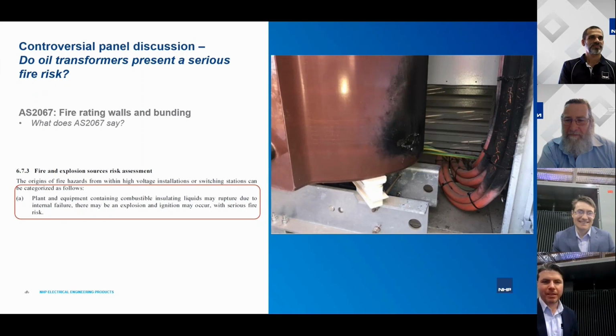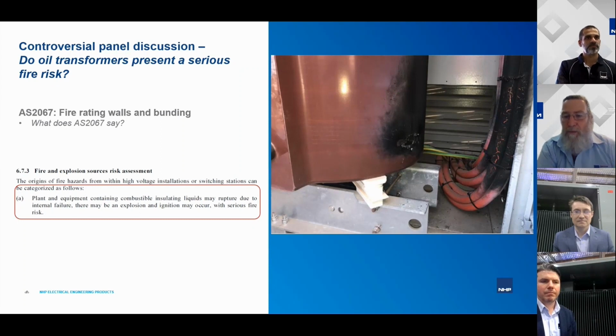Sean, you've obviously being the granddaddy of oil transformers, you probably have a few things to say about this question. Do oil transformers present a serious fire risk? What are your thoughts on it? I guess one way of looking at it, especially with the cast resin materials being self-extinguishing, we can look at that as being an endothermic reaction. So, in other words, as long as there is power on the transformer causing arcing or whatever the event might be, the reaction will happen. But as soon as that source is removed, then it extinguishes itself, and the result is what you see on the screen there.